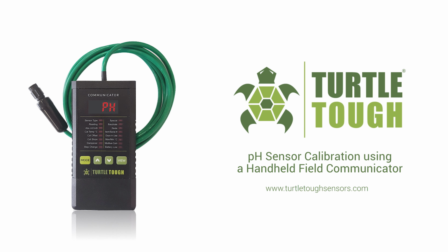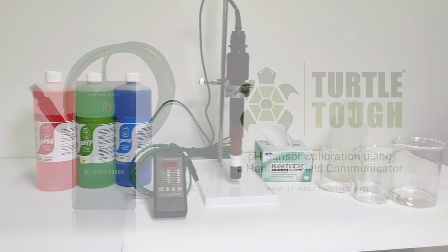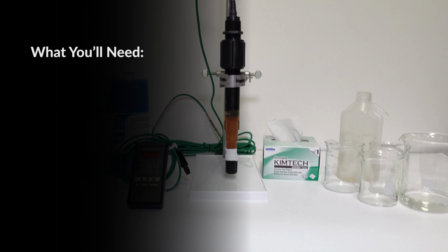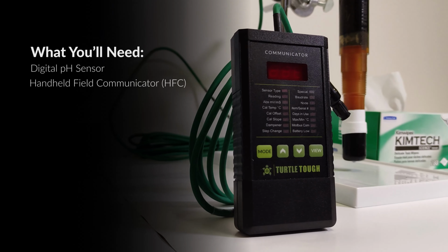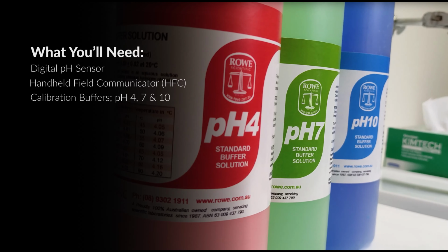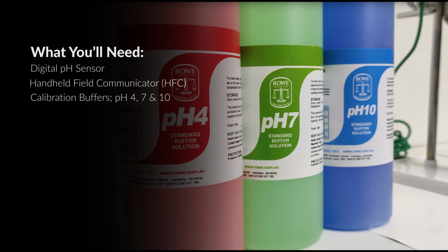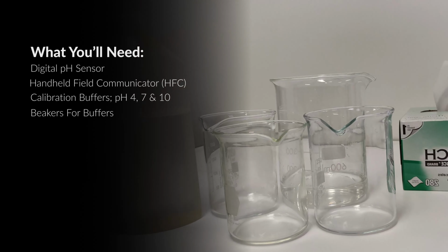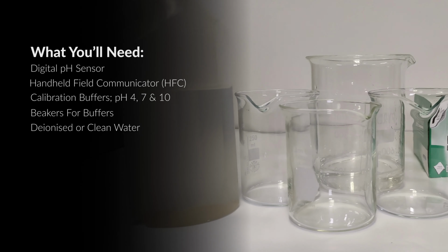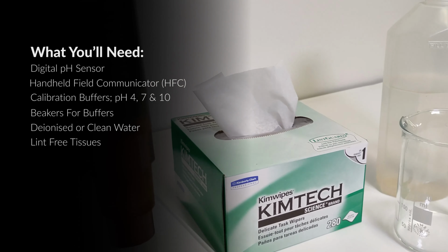In this video, we are going to show you how to perform a 3-point calibration of a TurtleTough pH DSS sensor using the TurtleTough Handheld Field Communicator, or HFC for short. To perform this calibration, you are going to need a TurtleTough pH sensor, a handheld field communicator, pH buffers with values of 4, 7 and 10, 3 beakers, deionized water, and a pack of lint-free tissues.